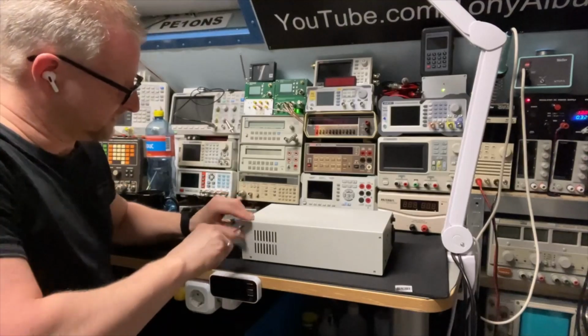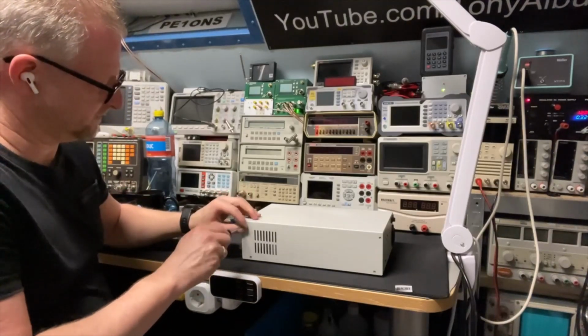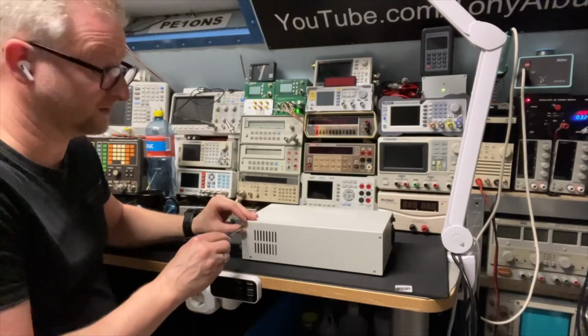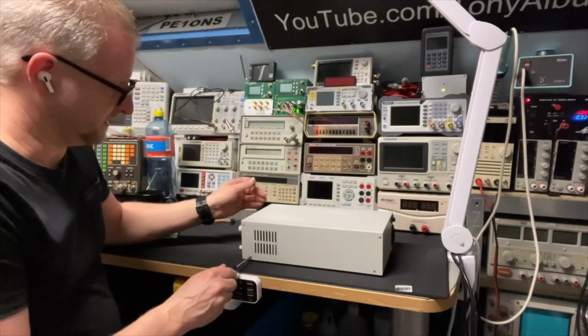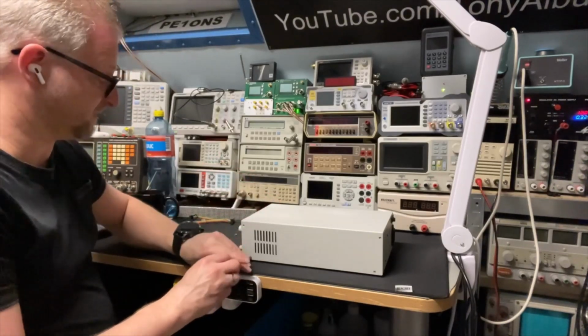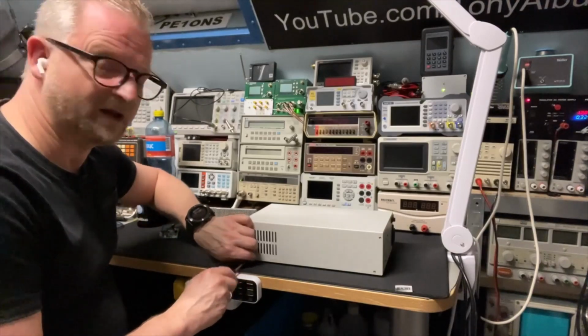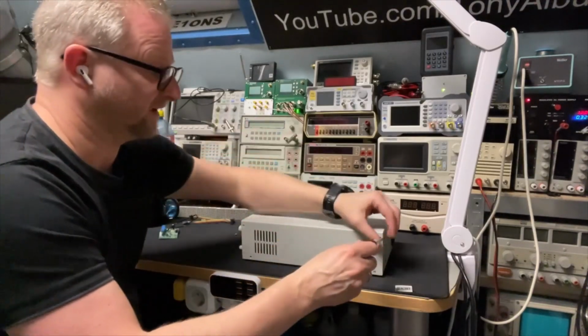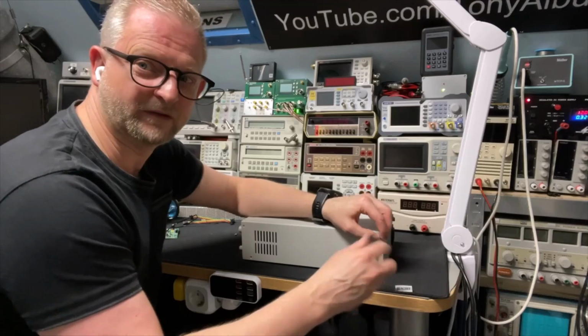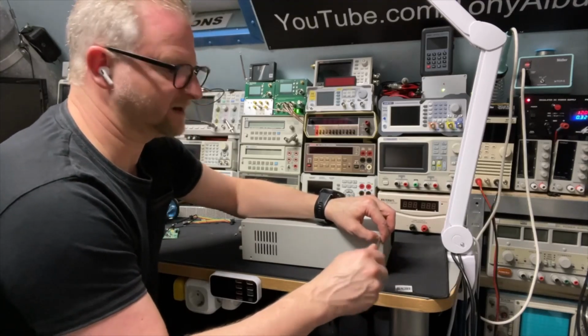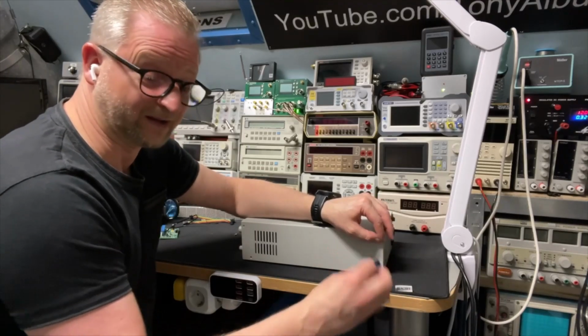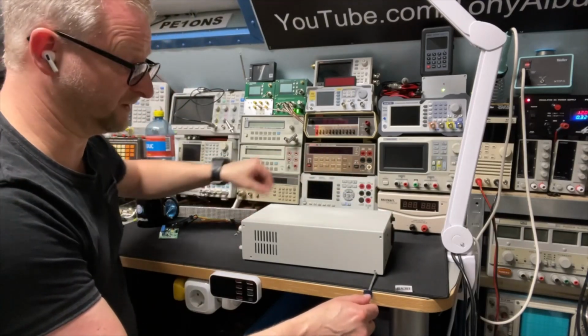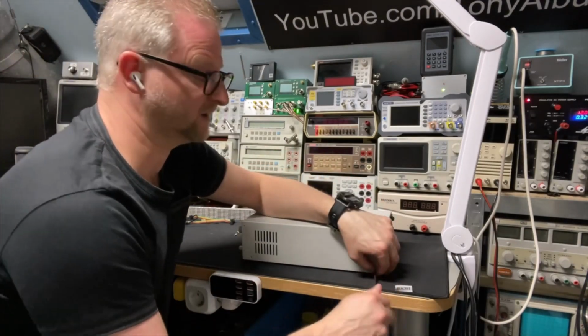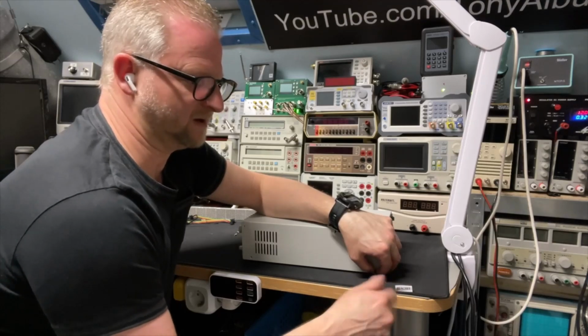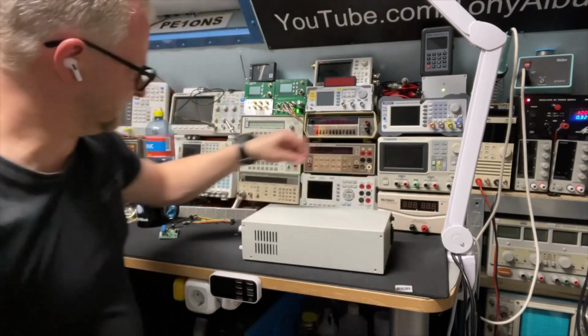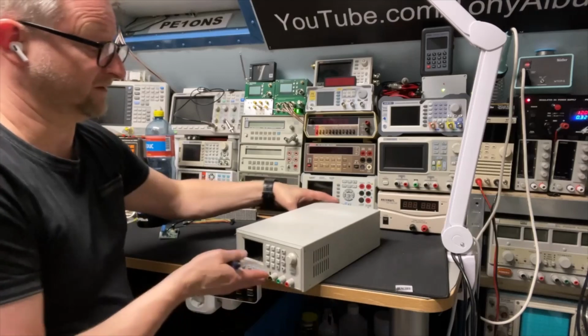The other time I made a complicated system because I didn't have PWM. I had one for 12 volts, then thought maybe I'd get one for 24 volts, but that wasn't possible because the fan was actually up to 29 volts. I looked at the regulator on the 24 volt board, and it went up to 25 or 26, but not 29, so I didn't want to risk it. That's why in the end I chose this 48 volt one, so we can be pretty sure it's enough.